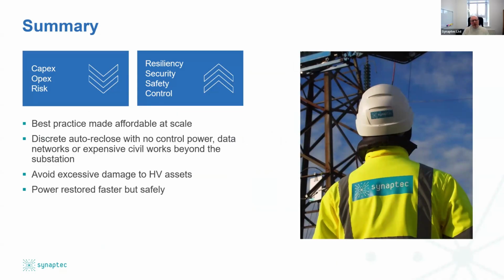But the summary of this thing is you can now deploy a multi-zone protection scheme without the traditional cost of the secure, dedicated telecommunications and data networking infrastructure, or all the substations that were traditionally needed at all the different points. So there's a fundamental reduction in the capital cost of instrumenting these systems. At an operational day-to-day level, clearly there's a saving because depending on where you started in your policy, you're either not running around looking for where the fault is and losing time that way, or you're able to avoid exposing cables and surrounding HV assets to that fault level current a second time and causing a lot of damage by reclosing incorrectly on a permanent fault.